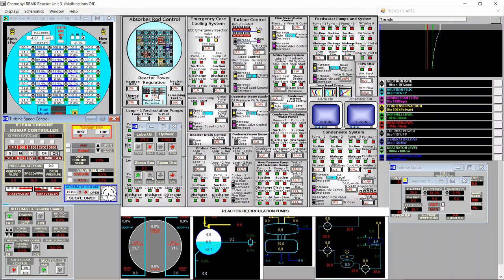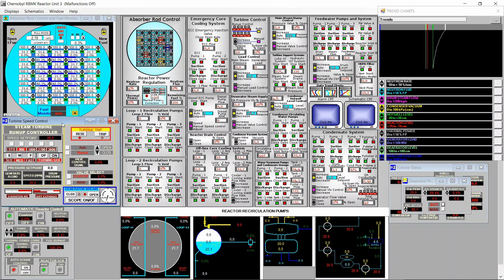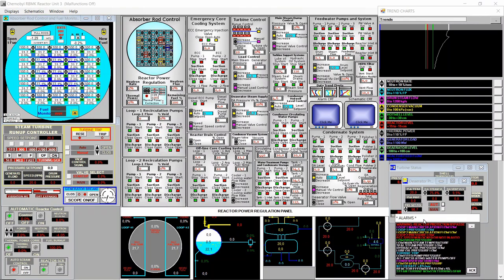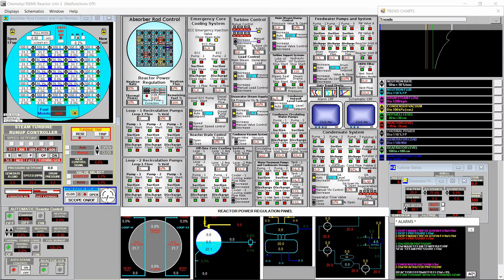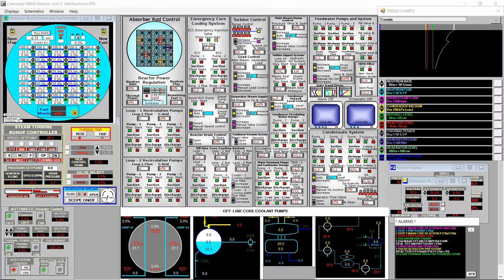Once the turbine is at 20 RPM we start the steam seal and close the dialogue. We need to keep an eye on the absorber rod control — the neutron rate is at five percent, so we decrease the withdrawal speed to medium. We don't want to surpass eight percent. We go to slow because we're at seven percent neutron rate, now at six.